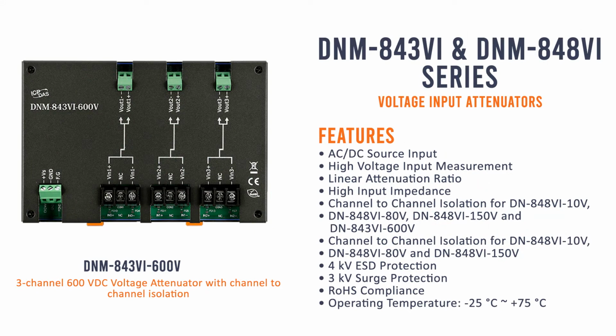The DNM-800V series are voltage input attenuators. The maximum input range is from plus or minus 80 V to plus or minus 600 V, and can be attenuated to plus or minus 10 V.